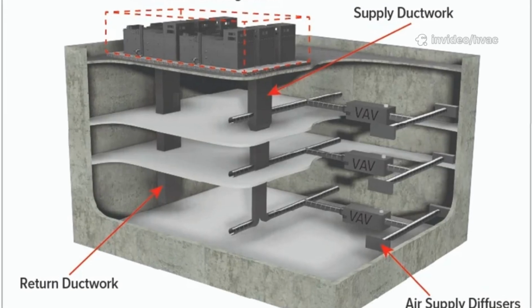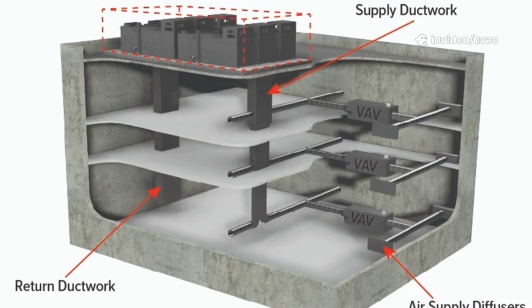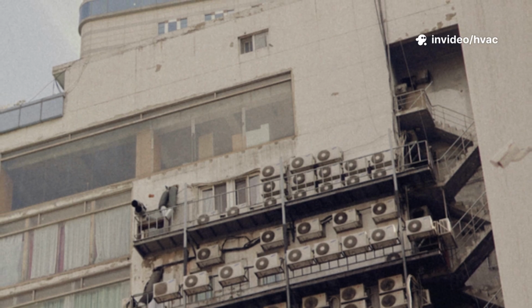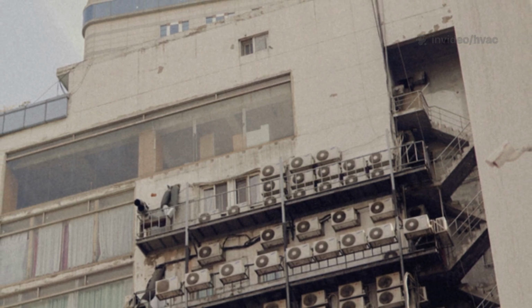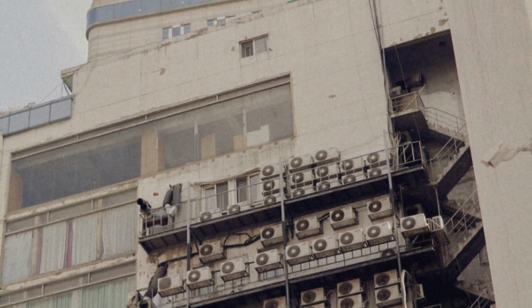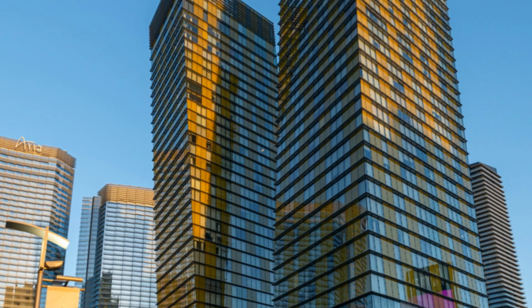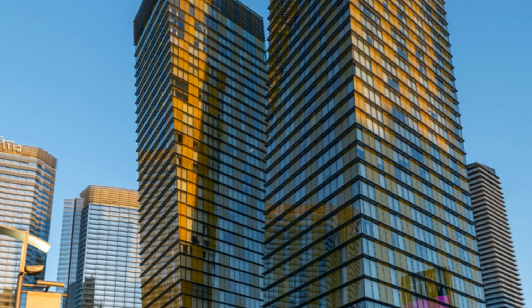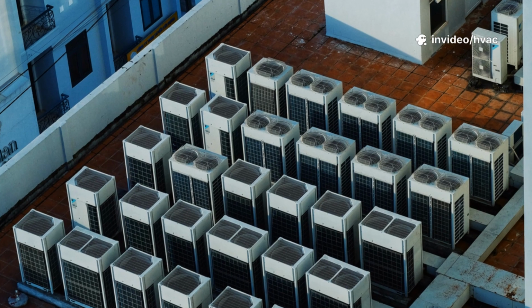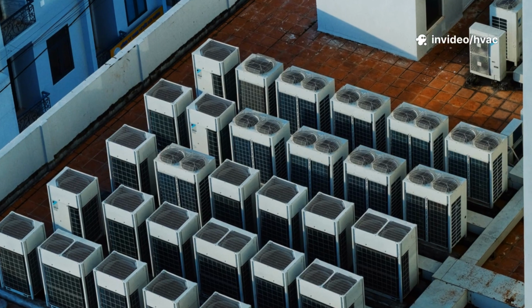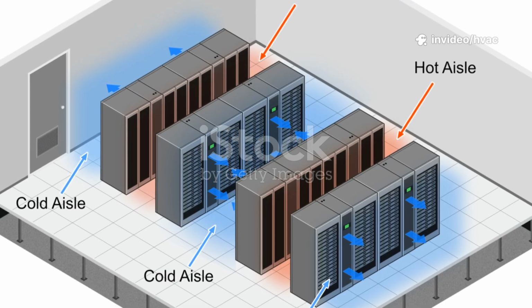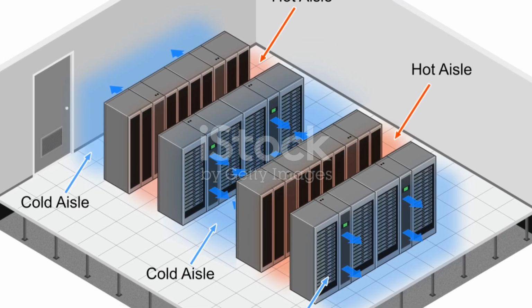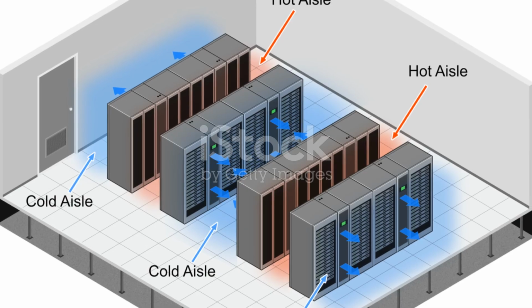VAV cooling-only systems are perfect for large buildings with diverse needs. Think office towers, schools, hospitals, and retail spaces, places with shifting loads and different uses. They shine in warm or temperate climates, where cooling is needed most of the year. In hot regions, the lack of reheat is a cost-saving feature. Even in cold climates, VAV works for interior zones that always need cooling, like server rooms or auditoriums.